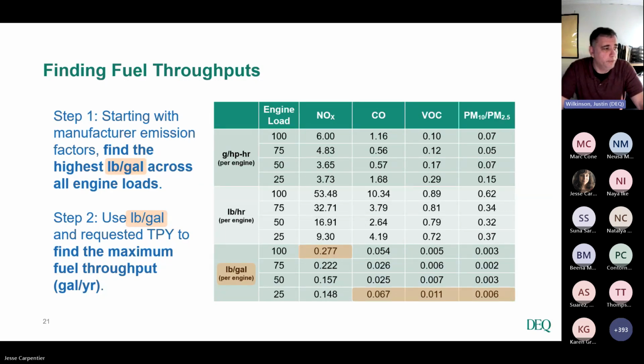In this case, we've identified the highest emission factor for this unit, which is 0.277 pounds per gallon. We're basically back calculating from that 100 tons per year. So if your limit is 100 tons at 0.277 pounds per gallon, it gives us an operational limitation of 718,000 gallons of fuel. That would be the federally enforceable limitation we could put on the source to keep them out of major source thresholds. So that's easy, right?